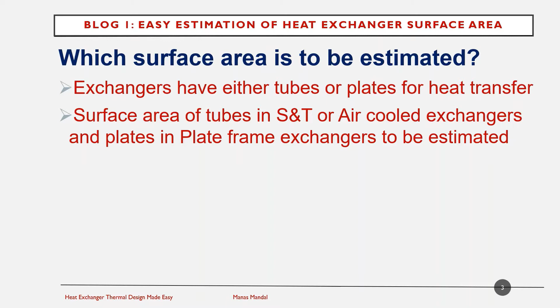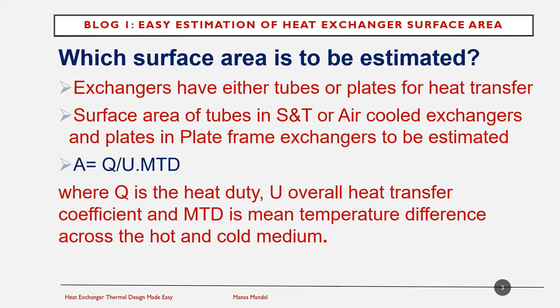Which surface area is to be estimated? Exchangers have either tubes or plates for heat transfer. So surface area of tubes in shell and tube or air-cooled exchangers and plates in plate frame exchangers are to be estimated. The main equation or the main calculation is around A equals Q by U by MTD, where Q is the heat duty, U is the overall heat transfer coefficient, and MTD is the mean temperature difference across a hot and cold medium.